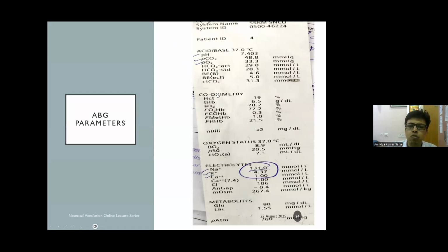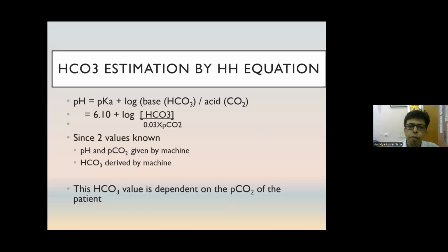Additionally, there is co-oximetry, which analyzes different components of hemoglobin as well as direct hemoglobin saturation of the blood, and some electrolytes, and finally lactate. These are the newer machines which give a holistic report.